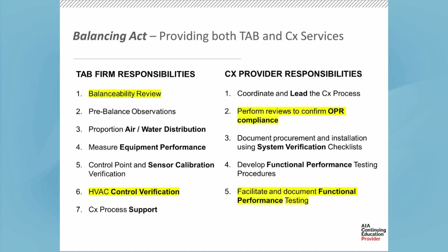So one thing to note: if the firm is providing commissioning services only, it's very important that they review - and this goes for any commissioning provider, but especially one that does both tab and commissioning but is only selected to provide commissioning services on a particular project - the tab specifications to determine what the requirements are on the tab side for control verification. Because if it's not included at all in the tab scope, it's going to determine more so what is done in the commissioning scope.